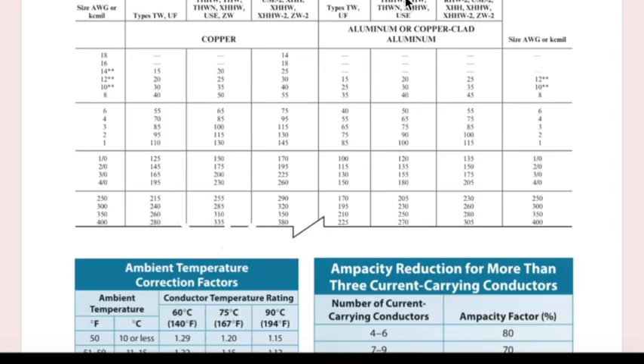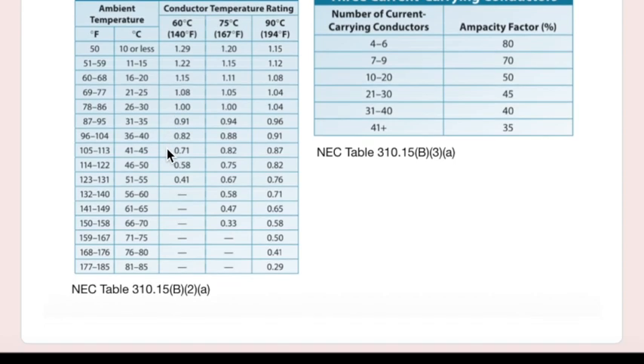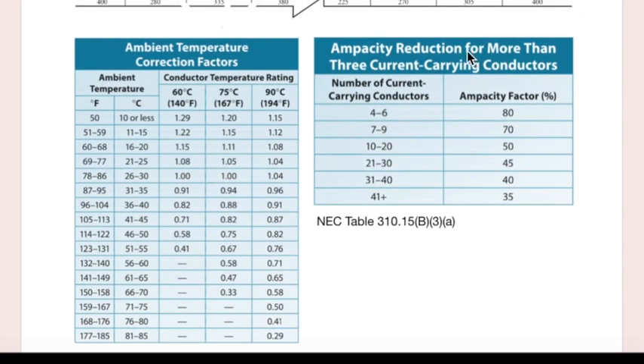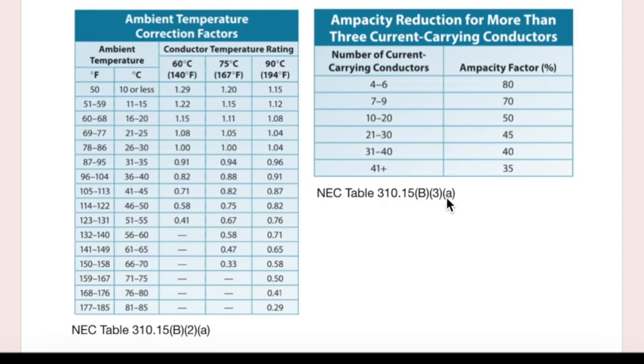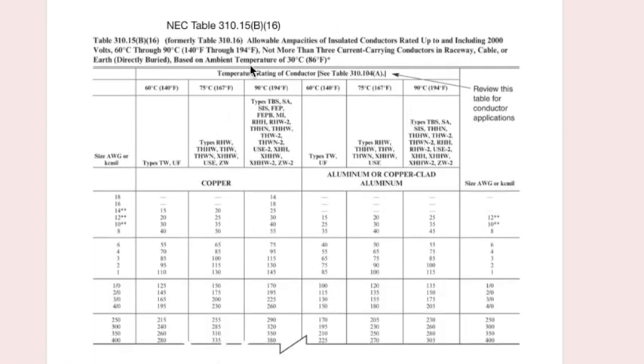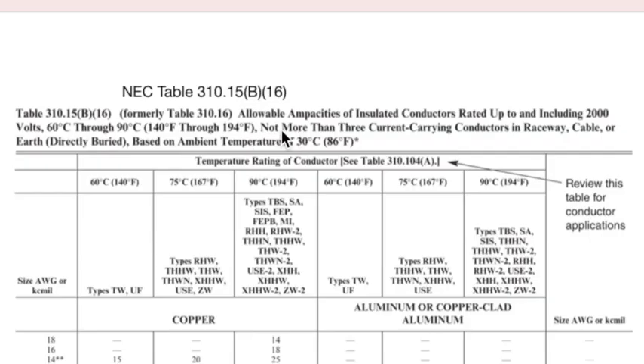Remember, these temperature ratings coincide with this ambient temperature correction factors chart, NEC Table 310-15B2A. And then our ampacity reduction because of current carrying conductors, or our adjustment factor, is 310-15B3A. So remember, we have adjustment factor, we have correction factor, and then we have our 'if the world was perfect' chart. If we had a conductor that was good up to 2,000 volts, if we had not more than three current carrying conductors, and we had an ambient temperature of 86, we would be in great shape. But we don't, so now we have to apply the adjustment factors.